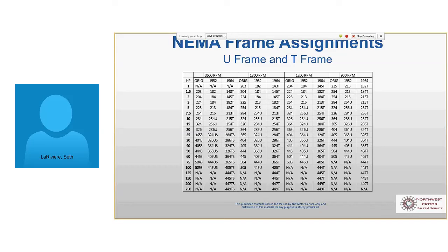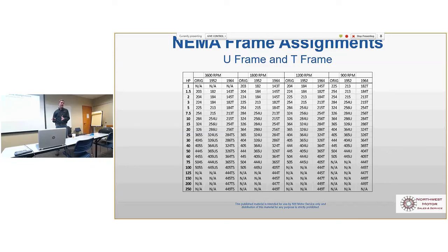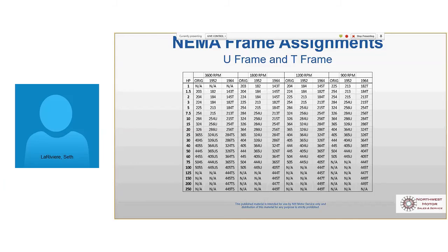And the problem is, and this sort of bites us, I keep using the word NEMA, which is National Electrical Manufacturers Association. Oh, close enough. NEC, right, in your world, the U.S. codes, right? Versus IEC, metric, that side of the world. Our stuff is robust. It's designed with overload built into it, service factor, extra load, extra capabilities that the IEC devices just don't have. So if you're using an IEC starter, the contacts are tiny compared to a NEMA starter. They're like 4 times as big on a NEMA starter.